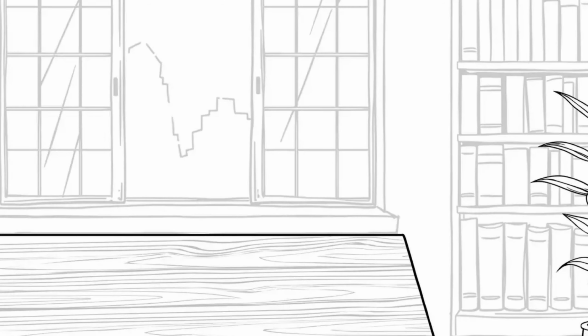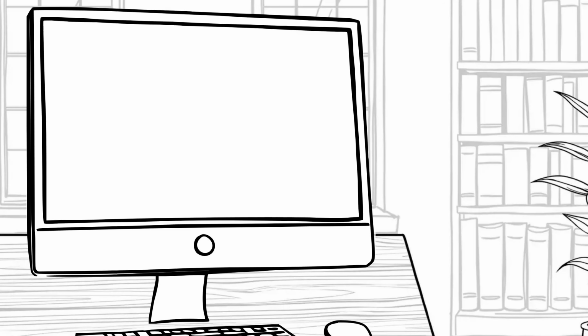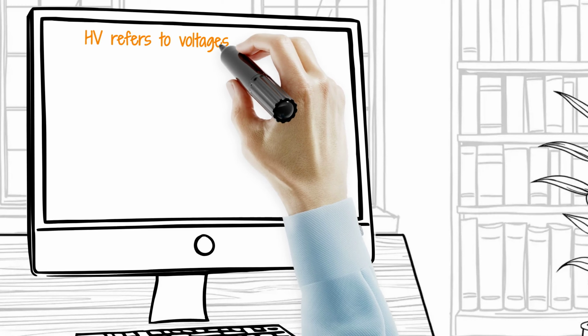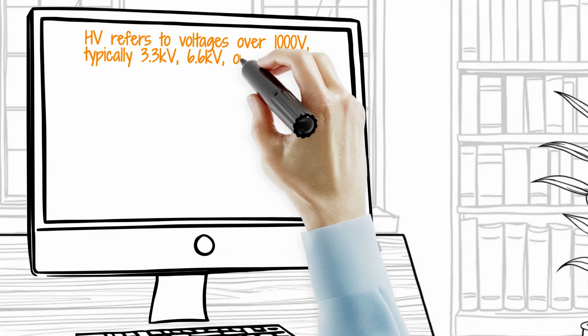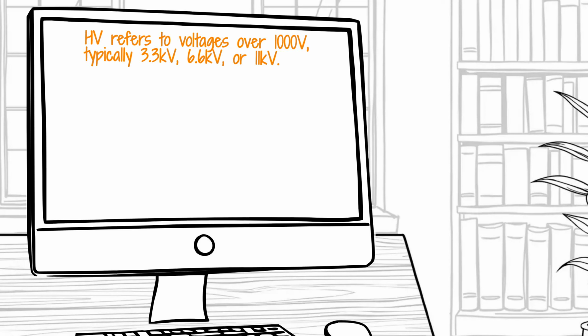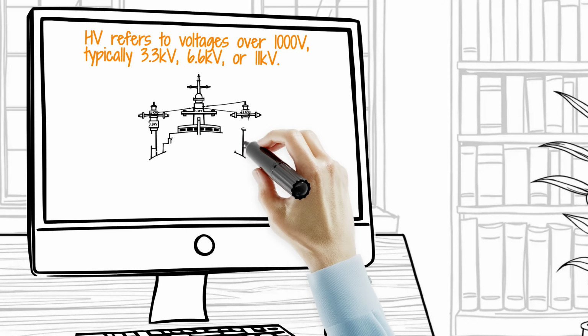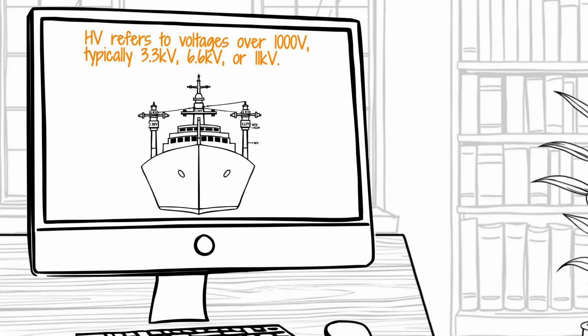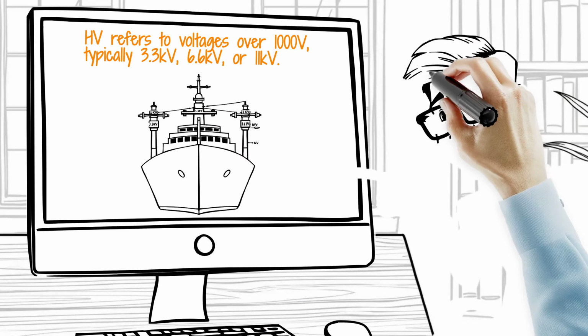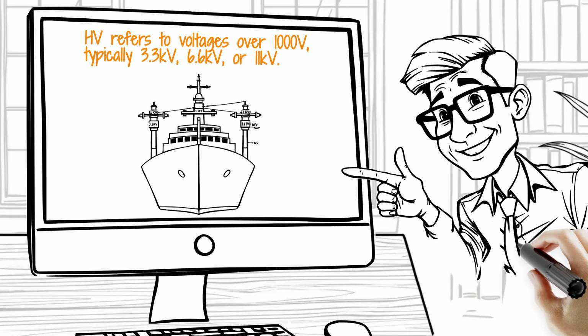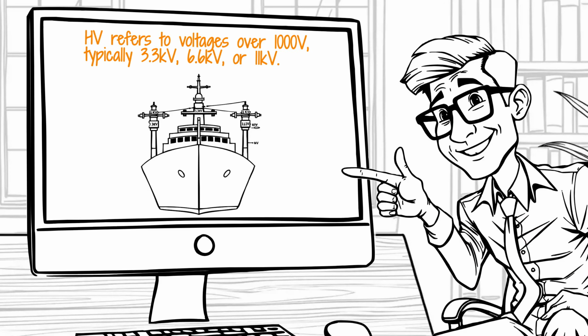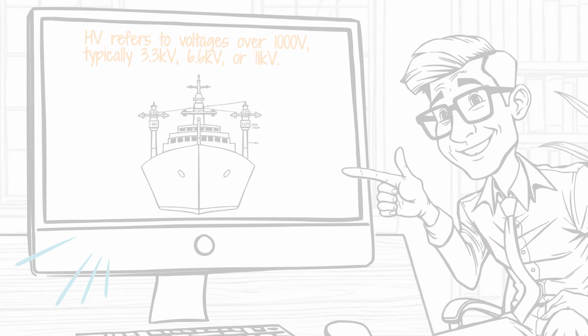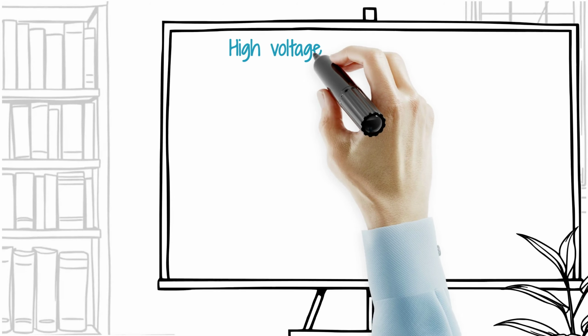What exactly is HV on a ship? While definitions vary, it generally refers to any voltage exceeding 1000 volts, 1 kilovolt AC, with typical marine systems operating at 3.3 kilovolts, 6.6 kilovolts, or 11 kilovolts. These high voltages are used because they allow for the transmission of large amounts of power with lower current, which means smaller, lighter, and more economical cables can be used. This saves significant weight and space, which is a huge advantage at sea.